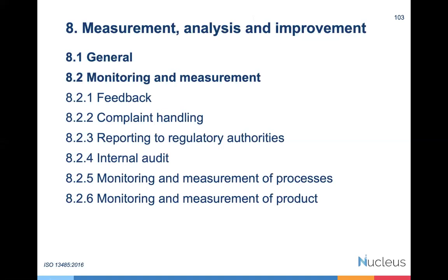The intent is to comply with regulation, and here is an example. Take a syringe — if a customer says the syringe creates a lot of pain and asks you to modify the design, that is customer satisfaction or customer delight moving in that direction. However, the intended use of a medical device cannot be deviated against customer satisfaction or expectation. You can ask for feedback on how patients or doctors handle and deal with a medical device — that is what the whole feedback clause addresses.